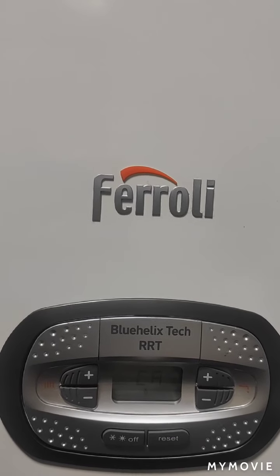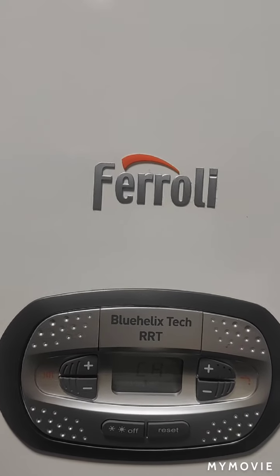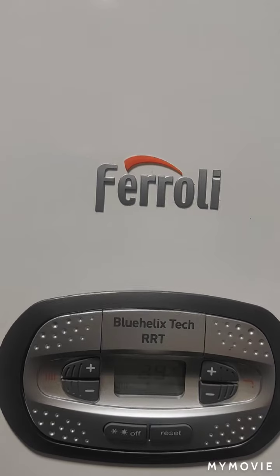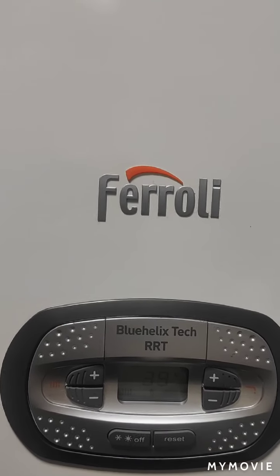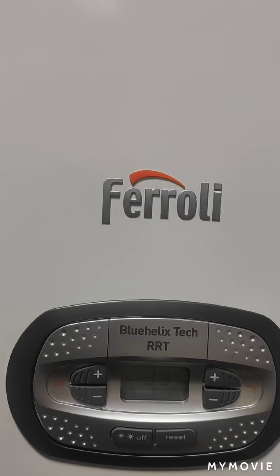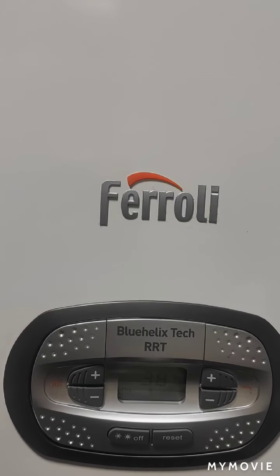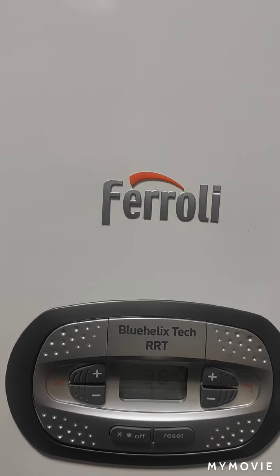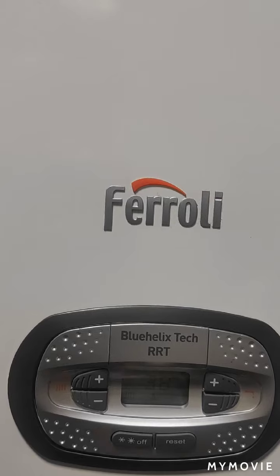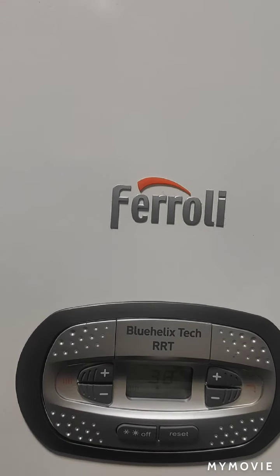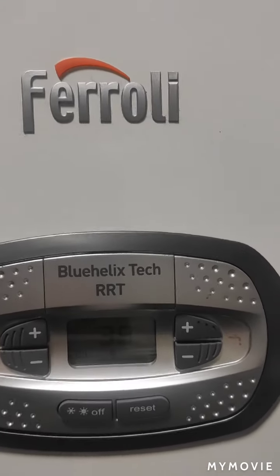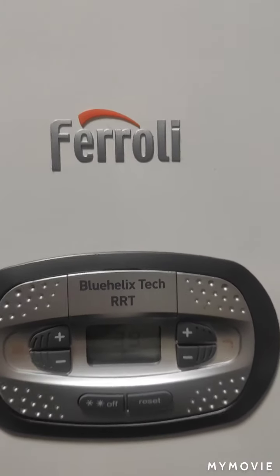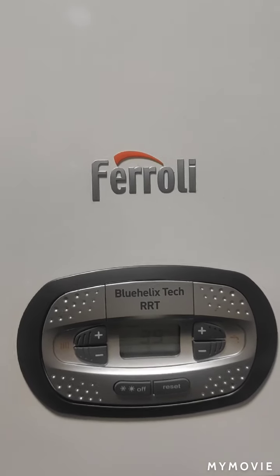If you ever clean the flame rectification or you change the electrodes, it's not something you need to keep doing. If you are going to clean the electrodes, you lightly clean them, because it needs that electrode to be working properly to get the readings properly. And that's the screen it goes back to once it's finished. And that's how you do the test mode and calibration on a Ferroli bluehelix.